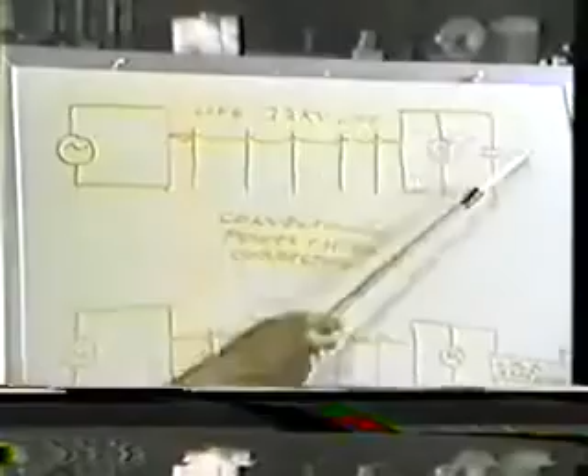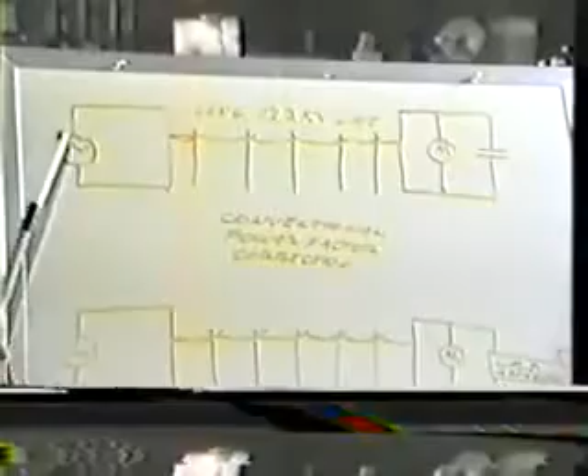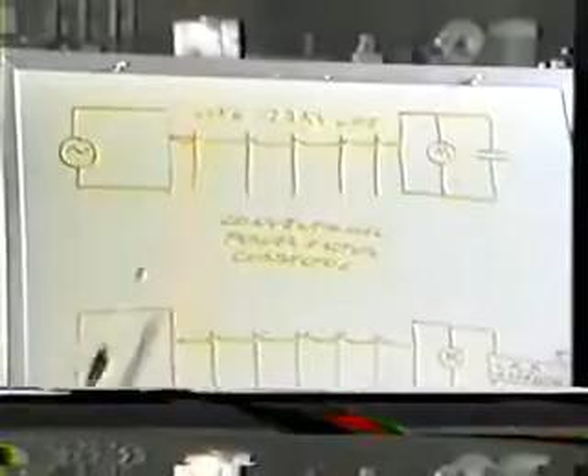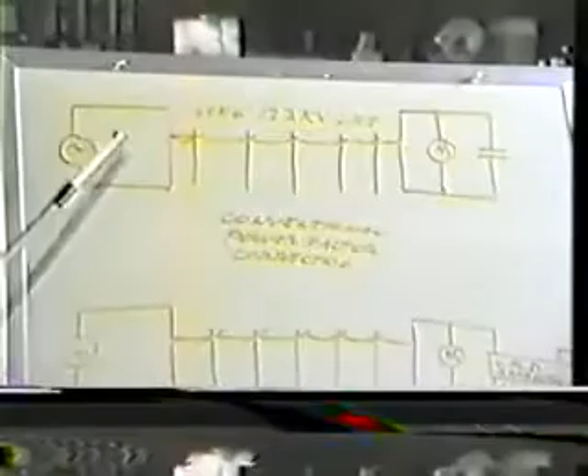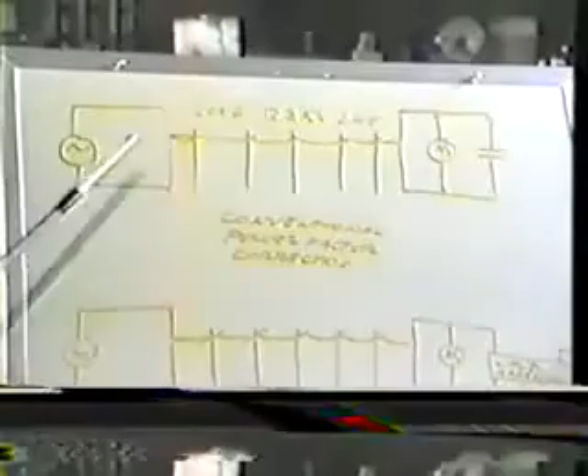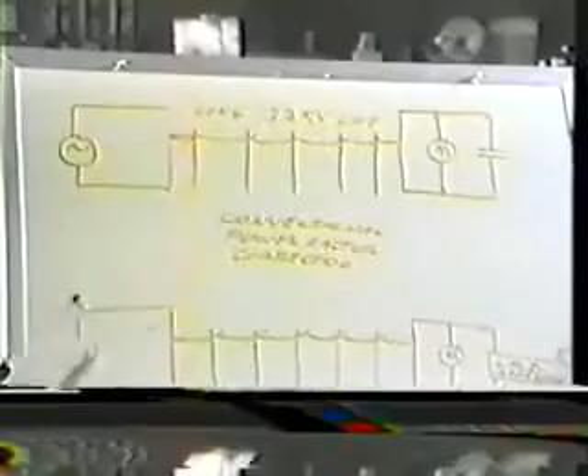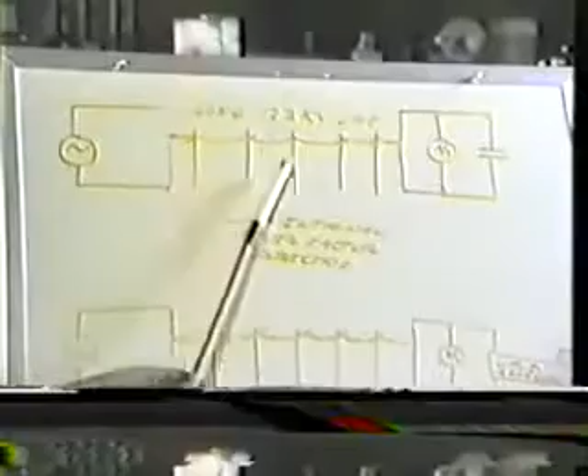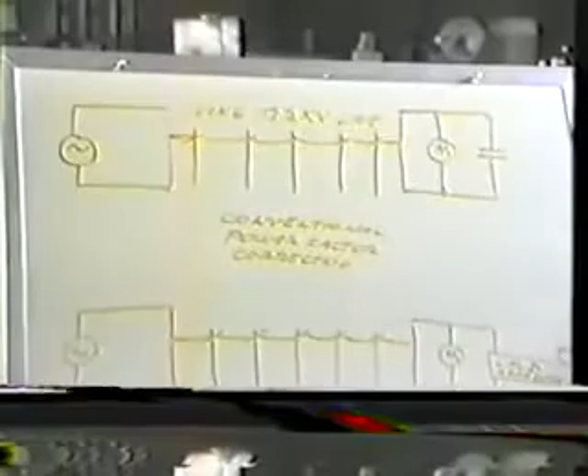The capacitor will resonate with the magnetic energy in the wire and cause the voltage of the system to raise as you go to the load, which is quite different than in normal DC circuits. So it's not uncommon in an AC power system that the voltage will start off nominal at the generator, usually 13.2 kV, and go up to 13.8 or 14, and if you remove the motor it would go up to infinity. When this happens, when the voltage gradient raises at the plant, the kilovolt-ampere reactive hour meter will start to turn backwards, which usually causes trouble with the power company.